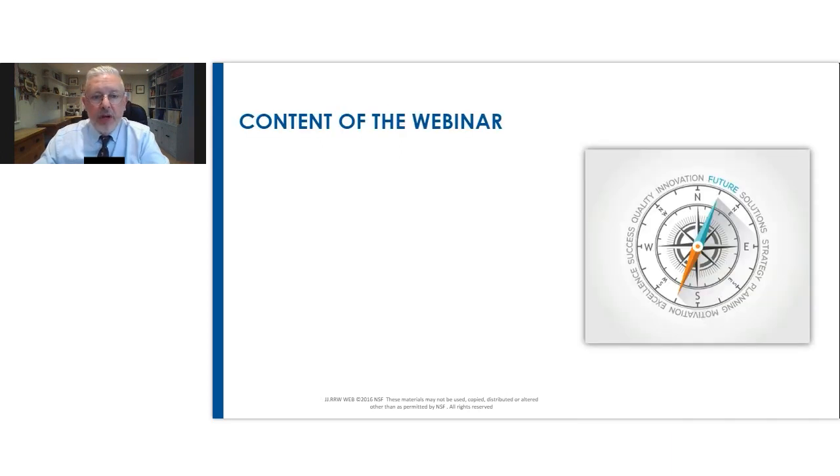We're going to talk about that point from receiving your FDA 483 report — so the FDA have done your inspection, they've left. Hopefully you've cracked open a bottle of champagne, or if it's gone poorly, a bottle of whiskey. You're now contemplating what happens next. Assuming the FDA 483 is lengthy, has systemic issues or issues related to misbranding or adulteration, you know the chances are you're going to get an FDA warning letter. That really feels like strike one — to use that baseball term — but it's absolutely recoverable if you do the right things in strike two and strike three.